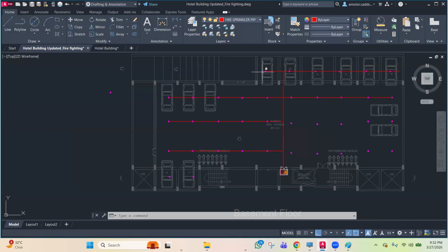Okay, this is the key difference between a sprinkler system and a curtain system. In a sprinkler system, only the sprinkler in the affected area is opened. But in a curtain system, all the nozzles discharge at the same time. So it is used mostly for fire barrier or glass protection, and it requires continuous discharge along the entire length. So flow is almost constant throughout the pipe. Hence, in most cases the pipe size is kept the same.